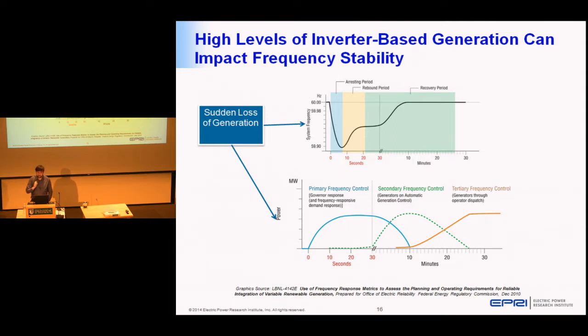The top graph though shows what happens when there's a fault on the system, that a generator drops out. If a generator has some problem and it suddenly disconnects at its substation, a large spinning mass on the system is suddenly disconnected. So all the other generation first of all sees this large dip in frequency because you end up having a less stable system. It all starts coming back online straight away though, by having this large spinning mass that it has. It stops the frequency dip from going too far, and most of the time, if not all the time, you'll make sure you don't end up having to shed some load to manage the generation supply balance. Obviously, if this was taken to an extreme, you'd end up having to shed all your load, but that has never really happened from a frequency perspective.